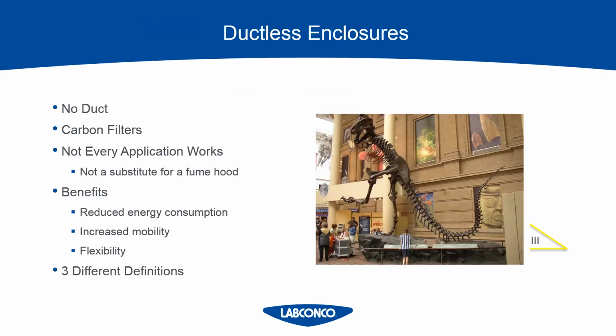So this is illustrating our first reason why you might want a ductless hood. You might really not be able to put some ductwork through the dinosaur. And so they were kind of forced in that position to have a ductless hood. We'll get into some more applications later, but basically these ductless hoods get their name because of a carbon filter pack that's located above the fume hood that cleans the air before recirculating it back into the lab. So they require no ductwork, just like their name says, ductless.